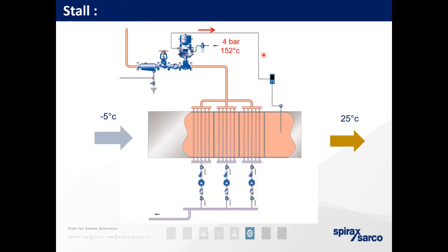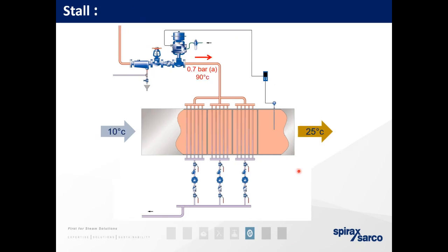So as it shows here, stall. This is heating elements for heating air effectively. We are in East Africa. I imagine there's not a lot of air heating systems here, but this is a very good example. So here you've got -5°C air coming in. You've got steam coils going through the vent, and that heats the air by radiant, allowing for 25°C out. You have to remove the condensate that's forming because it's giving up its heat, it's giving up its enthalpy. So you need trap sets to remove that condensate.